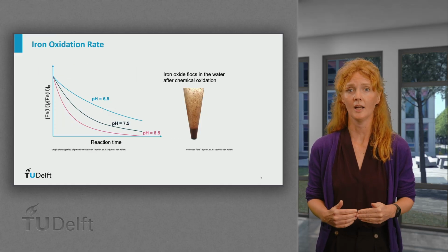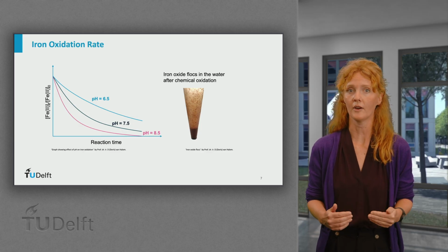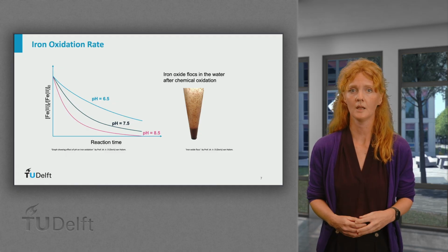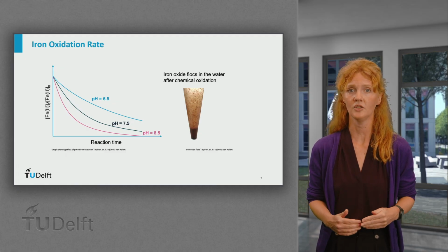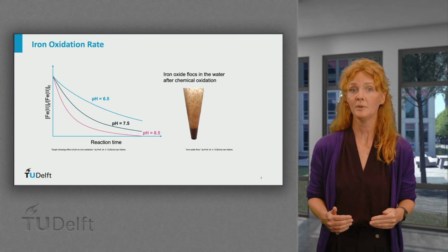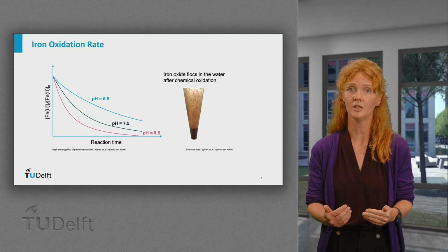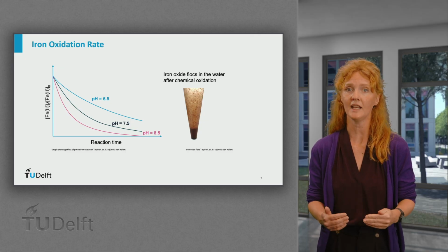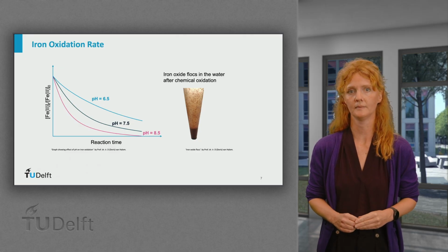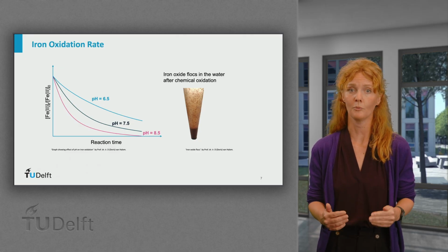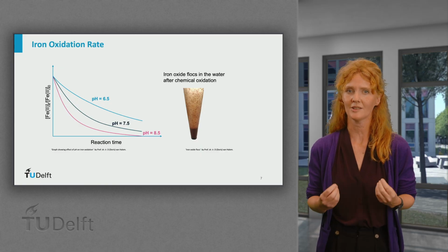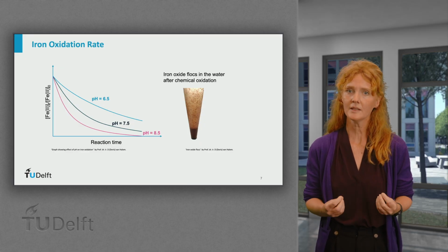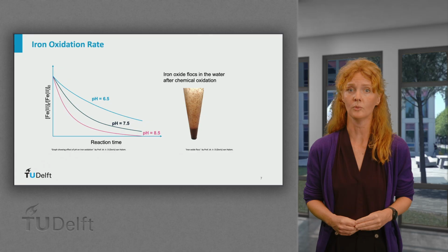While the rate of chemical iron oxidation to iron 3+ or ferric iron depends strongly on pH and oxygen concentration of the water, after aeration, oxygen concentration tends to be close to saturation, and the pH has increased due to the flush out of carbon dioxide. Therefore, iron oxidation will immediately onset in the supernatant water prior to filtration. The chemical reaction will result in the formation of ferric iron oxides, which are solid particles that will be trapped in the sand pores of the filter. Well, this is a traditional way of removing iron from groundwater.